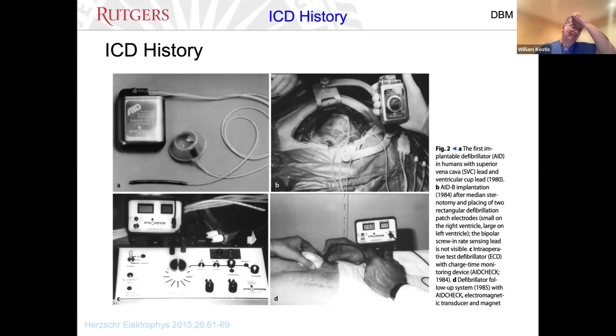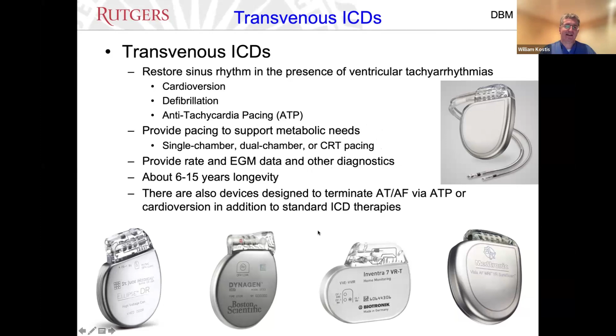So modern transvenous ICDs are much like the pacemakers, other than that they can also terminate ventricular tachyarrhythmias, either by a high voltage shock, which results in cardioversion or defibrillation, or via something called anti-tachycardia pacing, which we'll talk about some more. They can also be pacemakers, multiple chambers, or with CRT, and modern devices last between 6 and 15 years, depending upon various characteristics. And these are designed to prevent sudden cardiac death, excuse me.